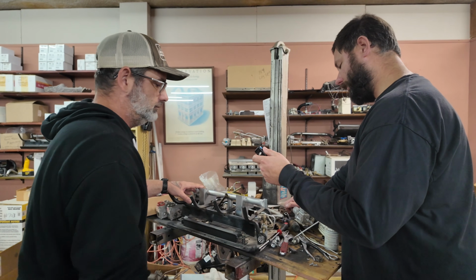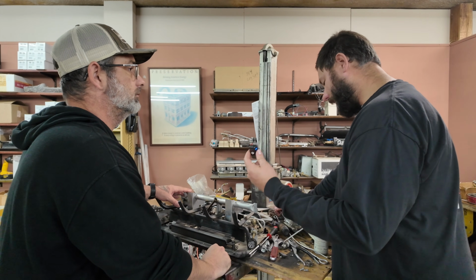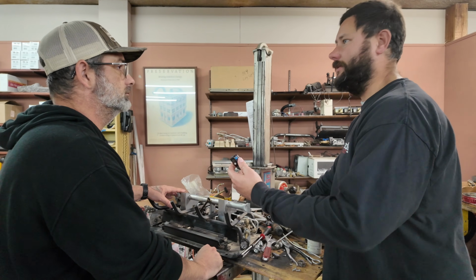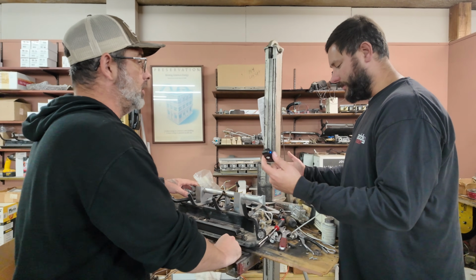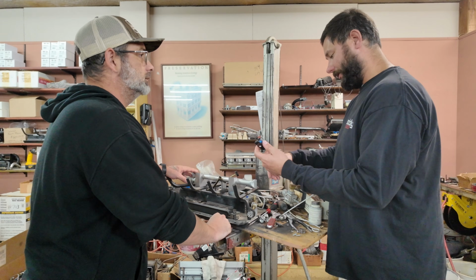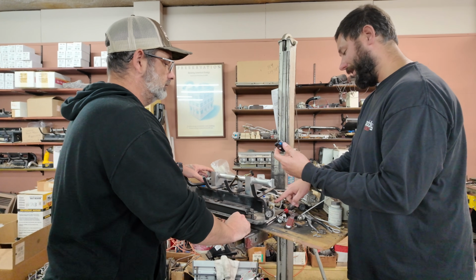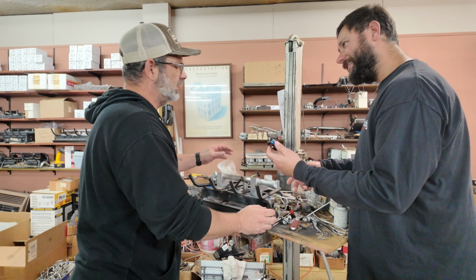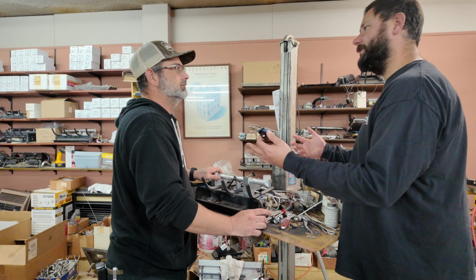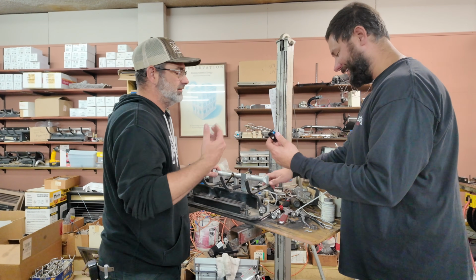Wow. Okay. So if somebody was using their logs and it went out and they tried to relight it, but they didn't wait until it was cooled and they didn't know that, they would think that something was wrong, but there's nothing broken or wrong. It's just the understanding of knowing that this pilot valve, it's a pilot valve, right? Correct. That this pilot valve has a what inside? It's a plunger system that's on there. And it just gets warm and it's basically expanded and then it won't basically turn back. Correct. Yeah, it's just kind of like a door.